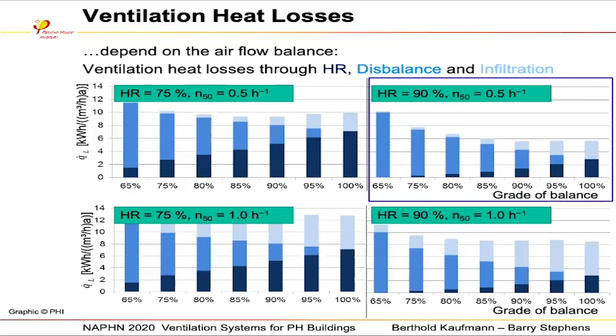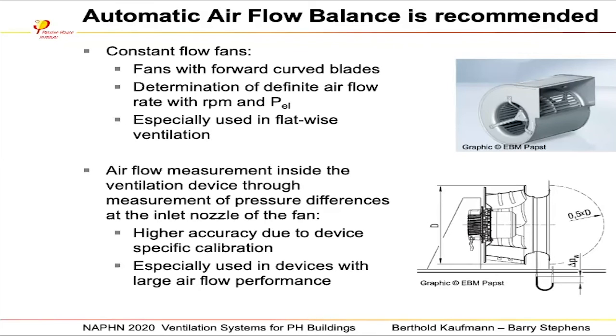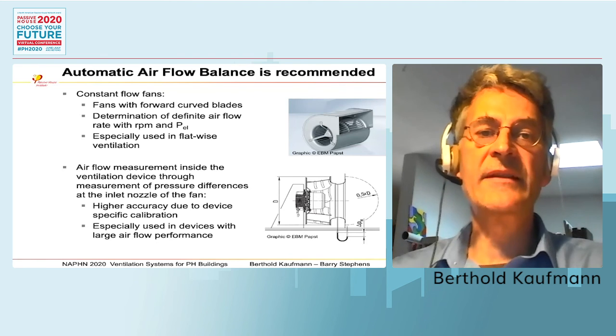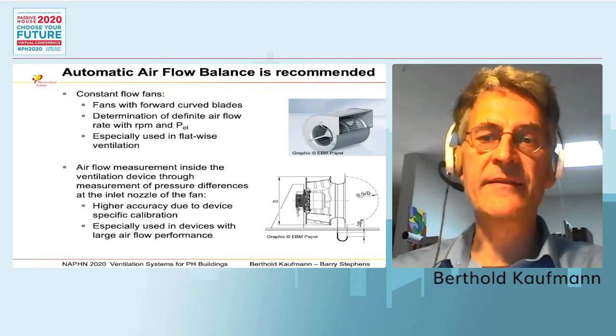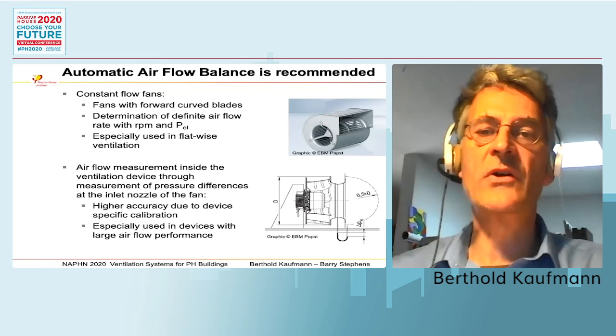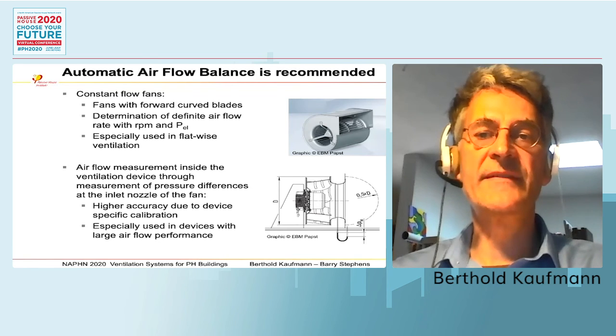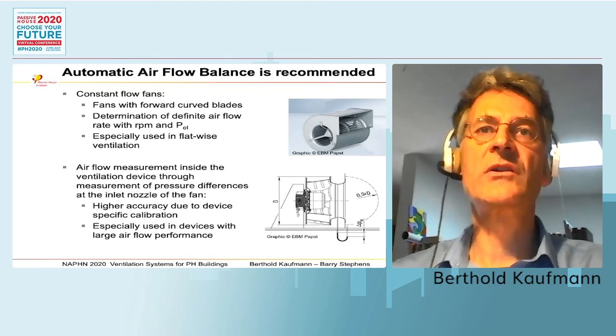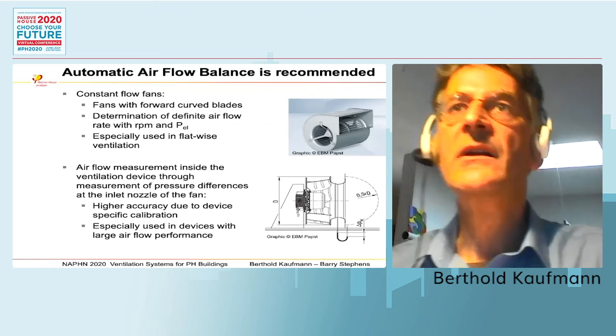Well, on the next slide, you see the airflow balance and how to realize it. The most simple thing nowadays is to have constant flow air fans. They are able to keep a constant airflow for a longer time. By the way, if a filter is in the system for a longer time, the pressure loss will get higher, and these constant airflow fans can compensate for this, so the airflow will be balanced for a longer time automatically. Newer systems and larger ventilation systems have had it included for a long time. The smaller systems are now getting better and better. But please care about this and ask the manufacturer to get this.